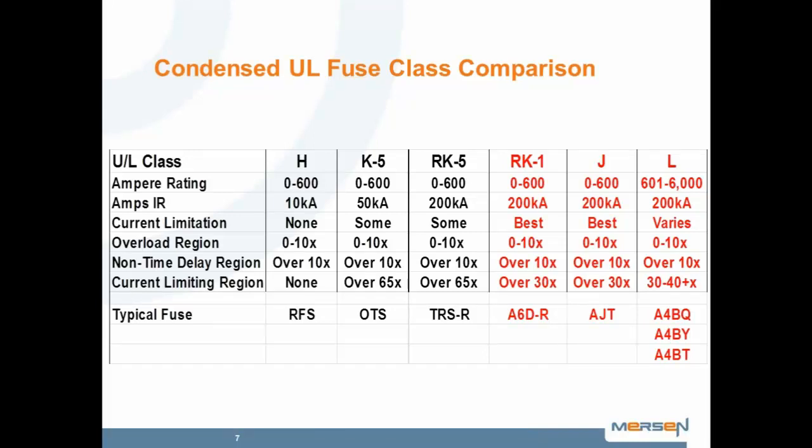The next one, and the last three are shown in red. Those are current fuse types that are recommended. RK1 has the same dimensions, or will fit into the standard fuse clips of the H fuse clips, K5 and RK5, in the same dimension.